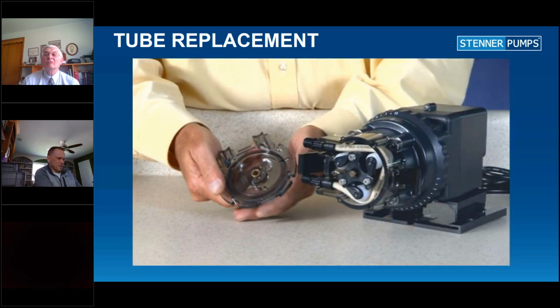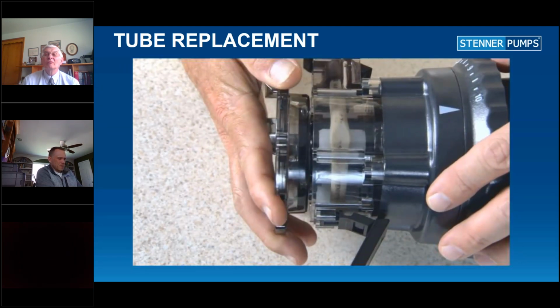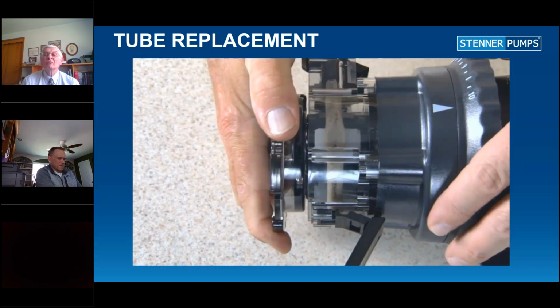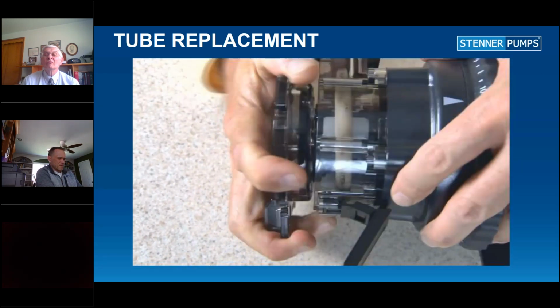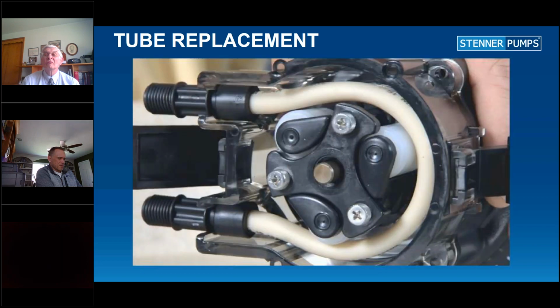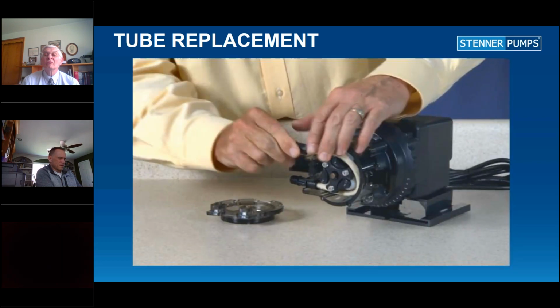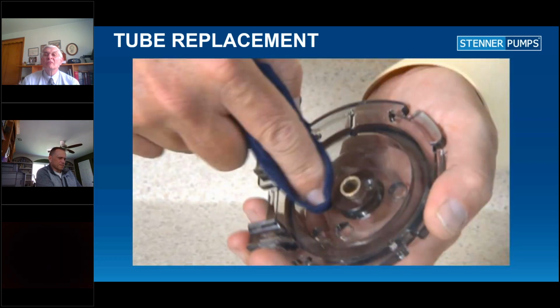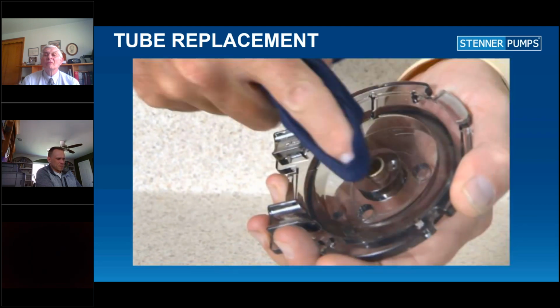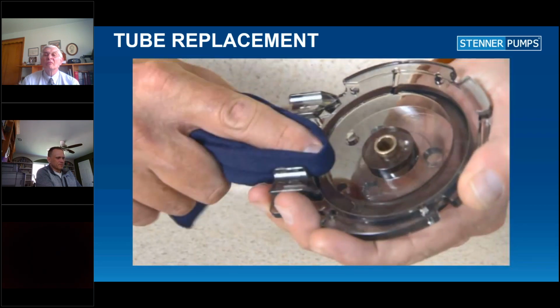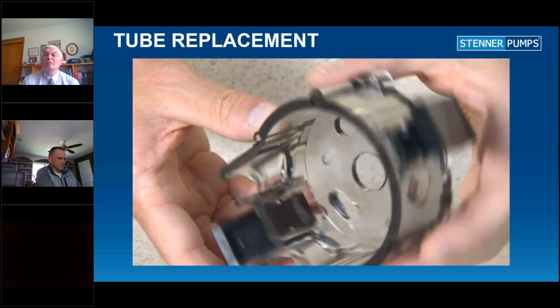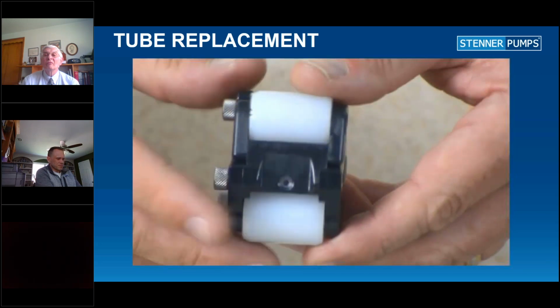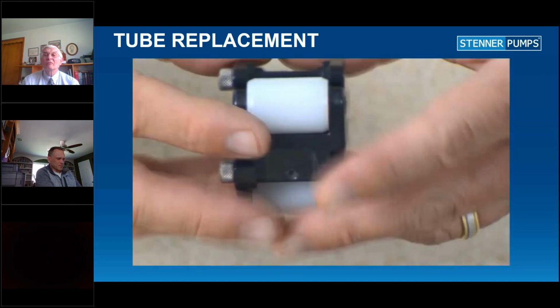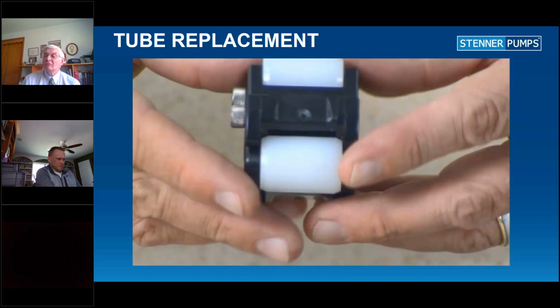What you're going to do is align the 3 holes in the cover with the 3 knurled lugs on the roller assembly. Hold the feed rate securely and use the cover as a wrench and quickly snap, rotating the cover counterclockwise to collapse the roller assembly. Remove the pump tube. Never install a new tube without rinsing the housing and roller assembly and wiping it clean of any chemical residue. In addition, check the housing for cracks and check that the rollers rotate freely and are not seized. Replace the parts as needed.